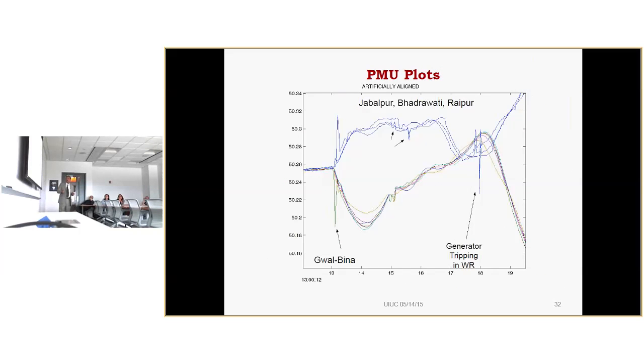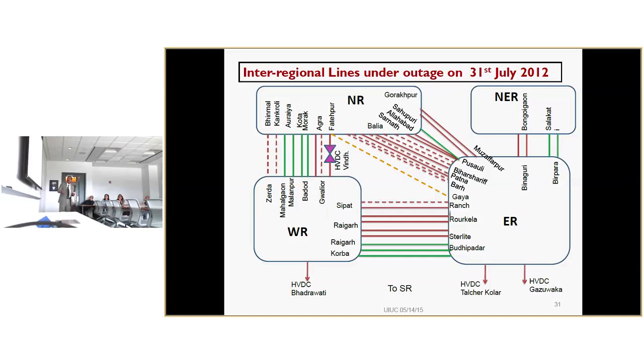And the eastern region, this is the eastern region. Somewhere here, a lot of 400 kV lines were taken out because of overvoltage. They don't have enough reactors to suppress the voltage. So a lot of lines in this region were tripped. And again, some of the lines were taken out for upgradation, and this link was weak. And they had connected one line and it tripped. They don't know what the reason was, I think. They were maintaining and they wanted to reconnect.